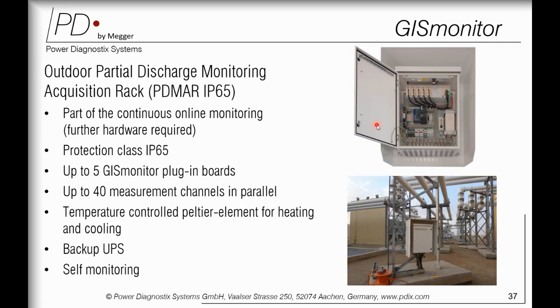That was for indoor. Let's say you have an outdoor condition where you want to install your GIS monitoring system, then we use the PDMAR IP65. It is completely IP65 rated. In completely outdoor conditions, it is also part of the online monitoring system, but it gives you capability for only up to 40 measurement channels. It is also completely temperature controlled, with a peltier-element with heating and cooling solution, backed up with UPS, and is a completely self-monitoring system.